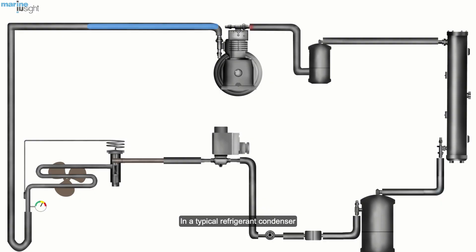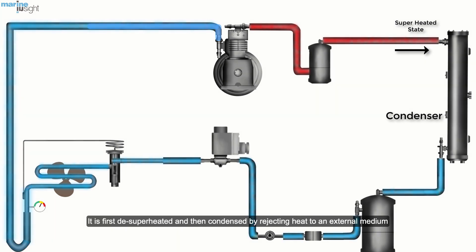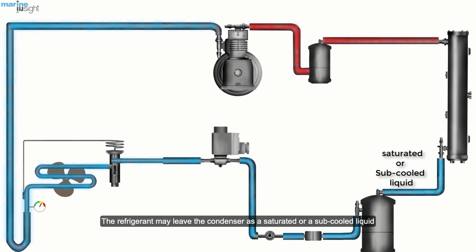In a typical refrigerant condenser, the refrigerant enters the condenser in a superheated state. It is first desuperheated and then condensed by rejecting heat to an external medium. The refrigerant may leave the condenser as a saturated or sub-cooled liquid, depending upon the temperature of the external medium and design of the condenser.